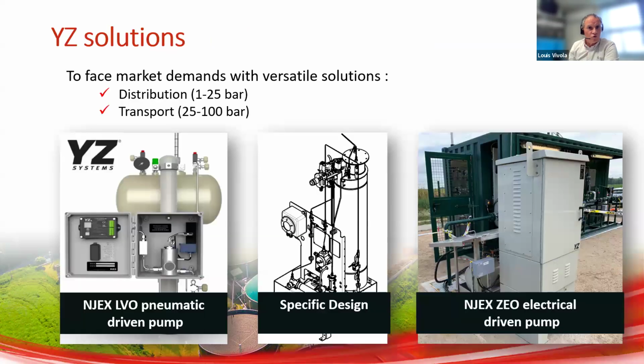YZ Systems odorizers are designed specifically for biomethane's low flow rate. Our models include the LVO, low volume odorizer, a simple and easy to use skid for low volume odorization. The ZEO, zero emission odorizer, a fully automatic electrical system dedicated also to a high level of odorization. And both systems can work together, or we can have a redundancy of equipment when needed, depending on the policy of each country. Next slide, please.